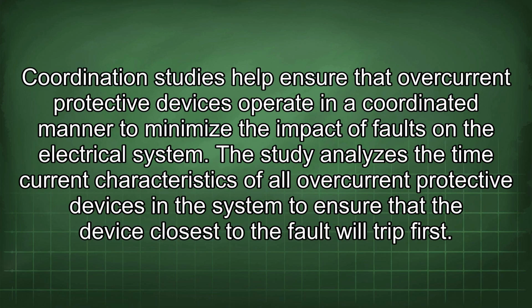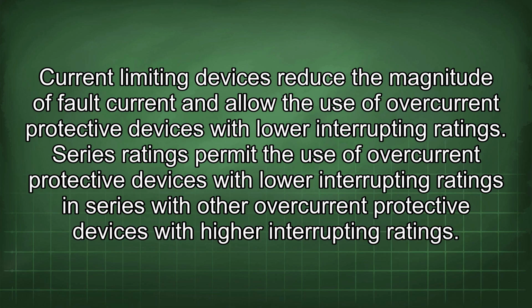Coordination studies help ensure that overcurrent protective devices operate in a coordinated manner to minimize the impact of faults on the electrical system. The study analyzes the time current characteristics of all overcurrent protective devices in the system to ensure that the device closest to the fault will trip first. Current limiting devices reduce the magnitude of fault current and allow the use of overcurrent protective devices with lower interrupting ratings. Series ratings permit the use of overcurrent protective devices with lower interrupting ratings in series with other overcurrent protective devices with higher interrupting ratings.